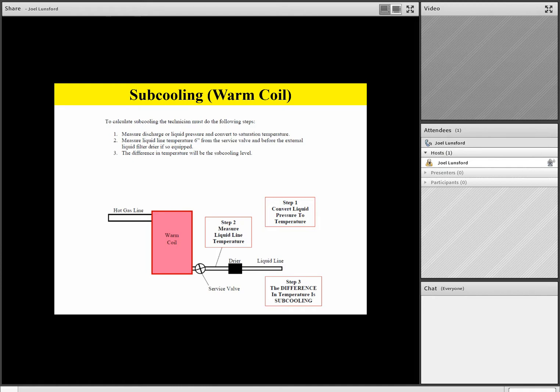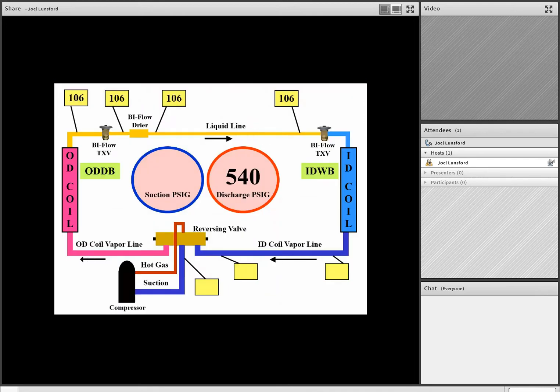So let's do one more practice before we get into diagnostics this afternoon. At 540 pounds of R410A, we see that we have a pressure temperature conversion of about 140 degrees, and the temperature leaving on our liquid line from the warm coil is 106. This happens to be in the cooling mode of operation. So the difference between 106 and 140 is about 34 degrees. So the outdoor coil is seeing 34 degrees of subcooling. That coil is flooded for whatever reason.